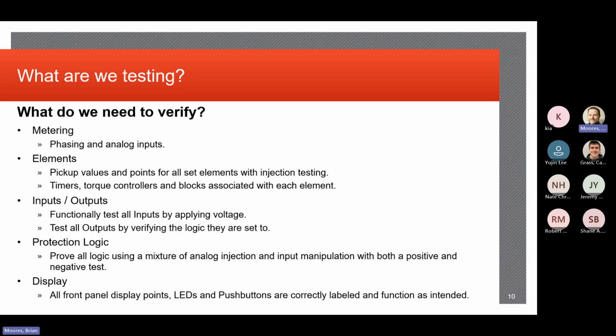Same with voltage. If it's 600 to 1 ratio, 1000 to 1 ratio, maybe it's hooked up phase to phase and not phase to neutral. So we're checking those things. So we check metering first to make sure, because remember, all the settings of a relay are going to be based on primary values through the CT and PT ratios, basically. So if we don't have that information in the relay correct right out of the gate, we're going to have a lot of problems downstream with all the other relay settings, because they're all based on primary amps, right? That's what the studies are going to be done in. So we double check that right out of the gate.